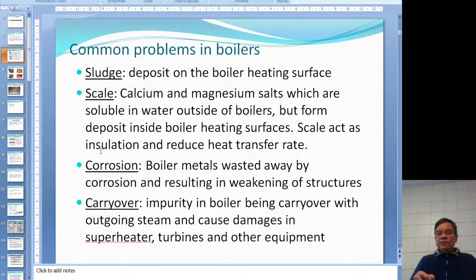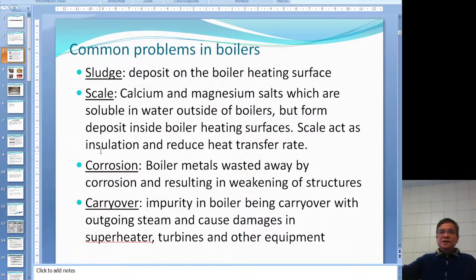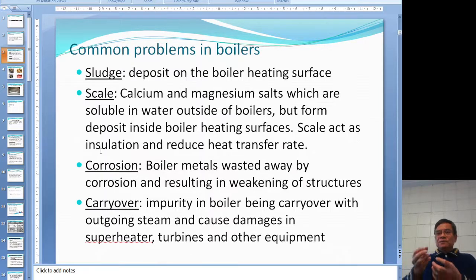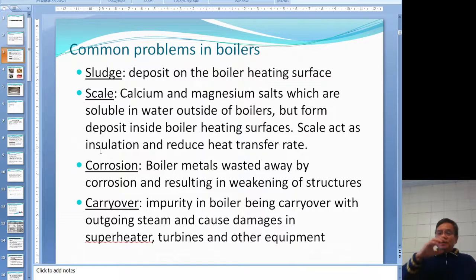Carry over is when something inside the boiler goes out with the steam. If the steam carries minerals to the superheater tubes, deposits form there. When steam with high carry-over minerals hits the turbine, it creates an imbalance. The clearance between the turbine blade and housing is very small, and you could ruin the whole turbine this way.